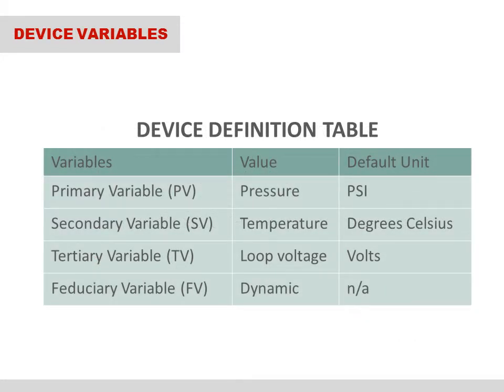The four device variables outlined in the device definition table represent the data or information that will be provided by the 815 PT via the analog output and the HART digital communication protocol. The primary variable, or PV, is provided via the analog outputs. The other three variables are provided via the HART digital communication protocol. Since the 815 is a pressure transmitter, the value provided by the primary variable is the process pressure, and the default unit is pounds per square inch, or PSI.